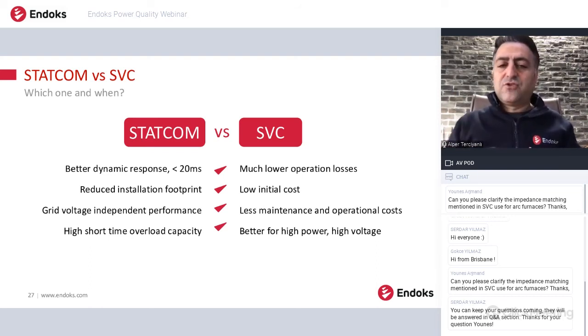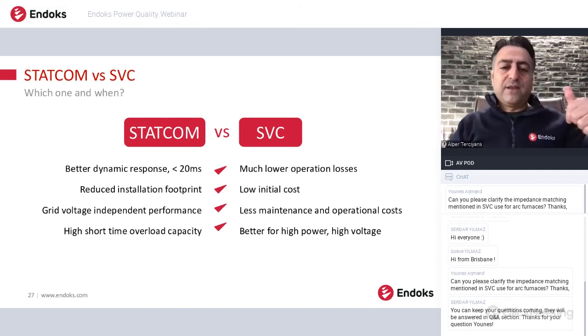We have a system in Australia right now, and we can inject 2 times rated power for 3 seconds with the STATCOM. But for SVC, we cannot, because the reactive power of SVC is limited by the passive equipment and also voltage, because the reactive power is equal to V squared over impedance, V squared over X. So if the voltage drops, reactive power drops, and if the voltage rises, then the reactive power rises.